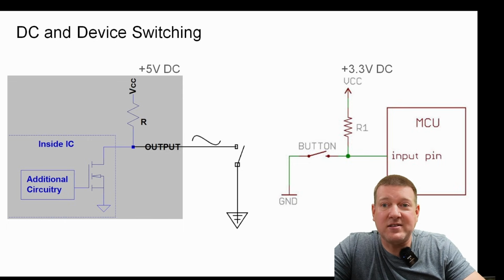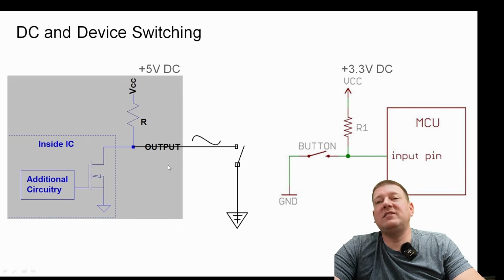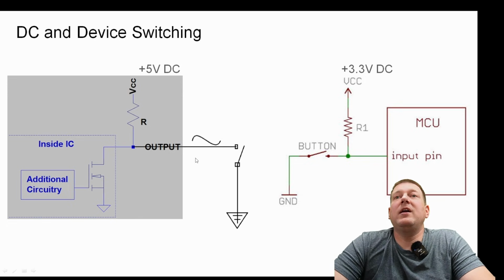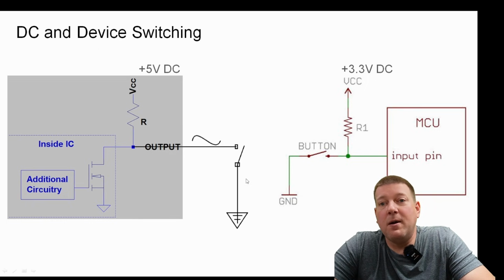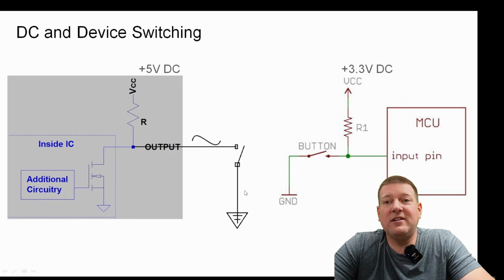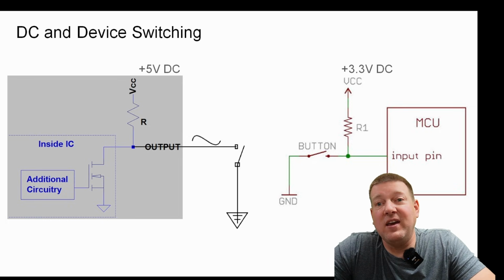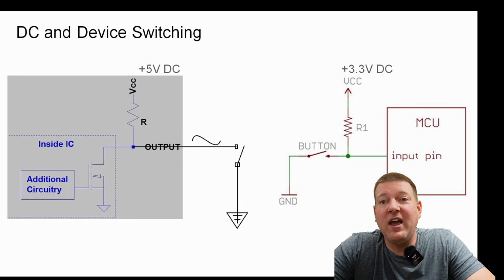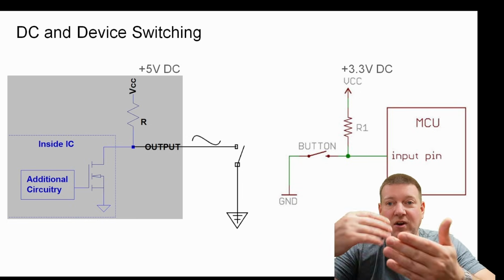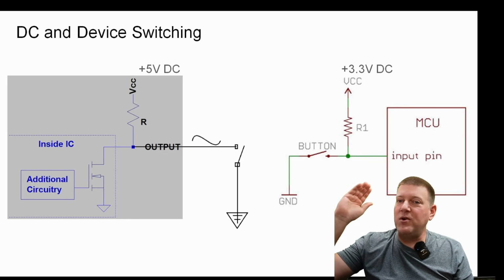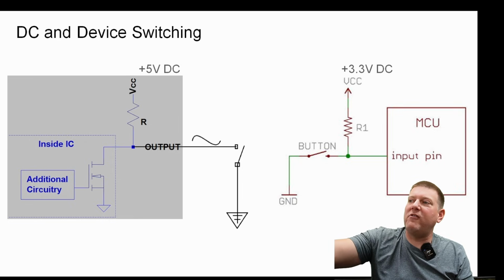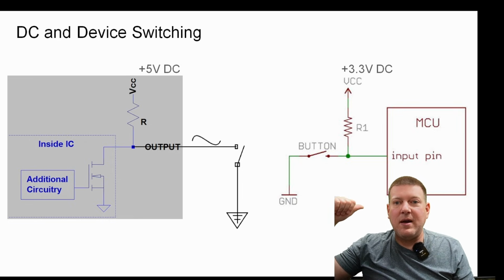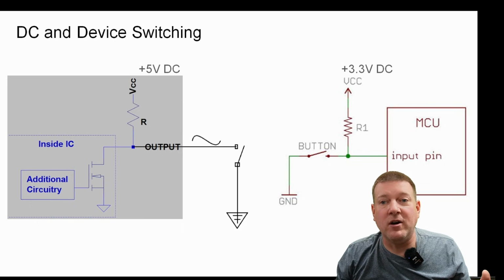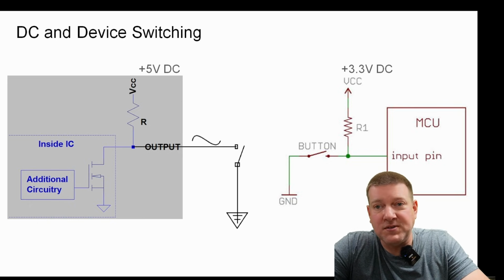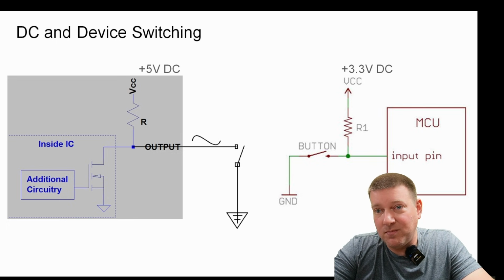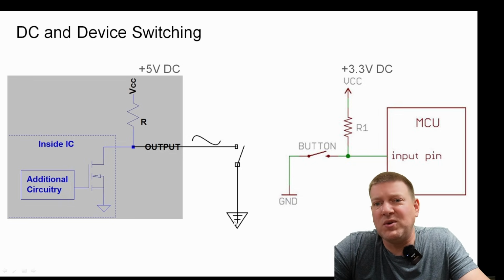If it's binary, it's going to mess up communications. But with a switch, let's say it's an emergency switch, if I have a false positive on an emergency switch or a homing switch, you could now make that device crash because it thinks that it is at the end of the line and it's going to go back this direction. Sometimes they'll count how many pulses it's going to go in this direction because it knows if I hit the limit switch, now I have to travel 200,000 pulses to get back to my home position or to be in the middle of the table or whatever. Those stepper motors and stuff, they just count pulses. So you hit a limiting switch, maybe even a door open switch, something like that. We'll go over switches tomorrow.